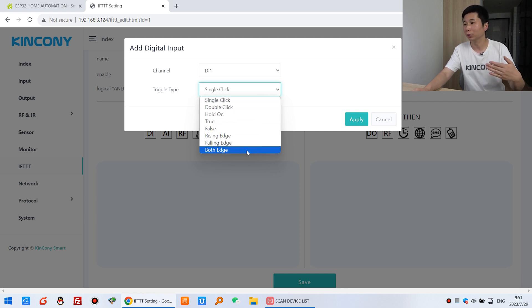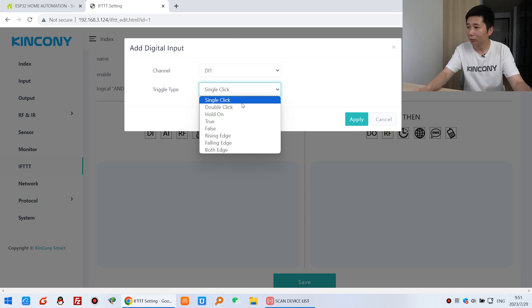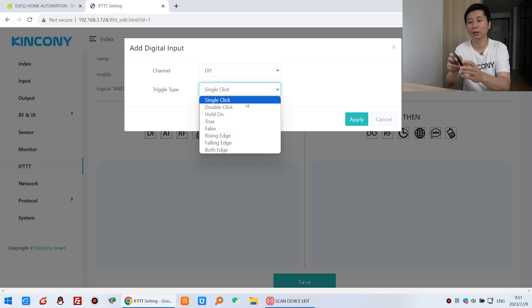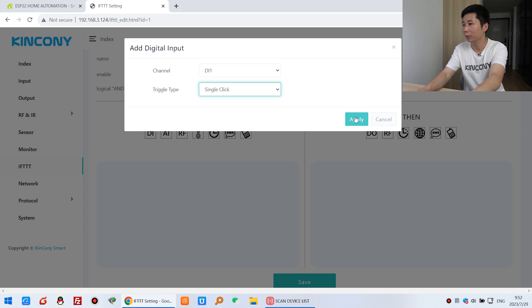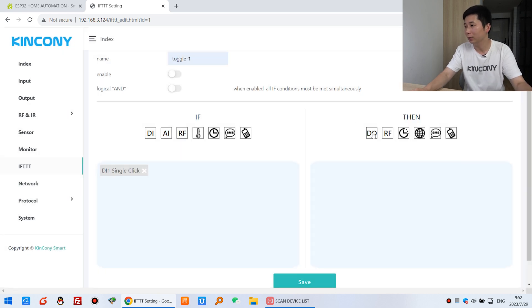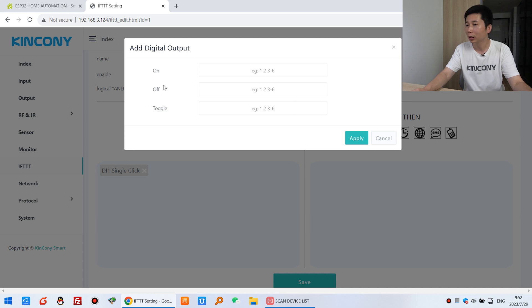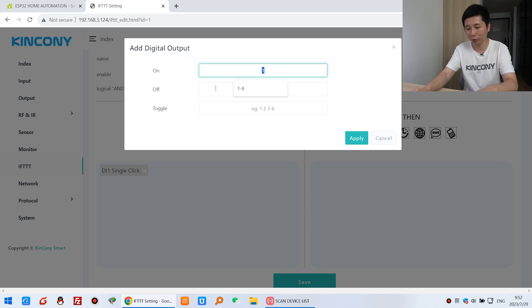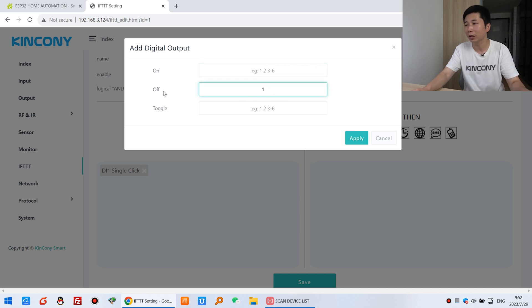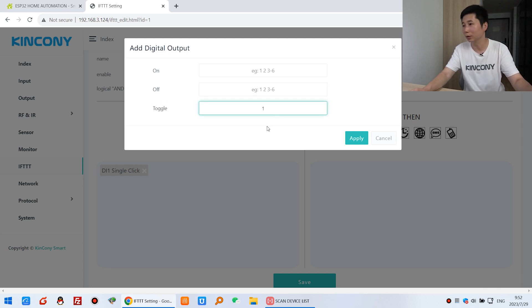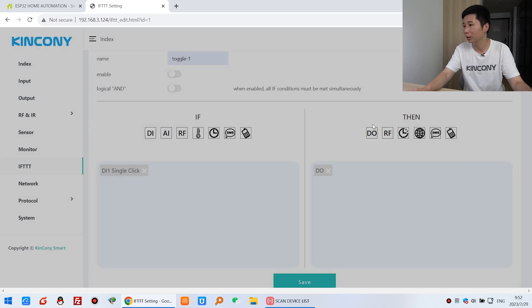I will tell you the difference between the trigger types. You can select single click — that means just one press. Click apply. The DO means the relay output. If you want to turn on relay 1, input 1. If you want to turn off relay 1, input 1 at the off setting. If you want to toggle relay 1, input 1 for toggle. I want to toggle relay 1, so I input 1 here and press apply.